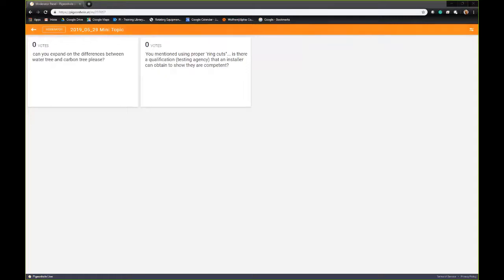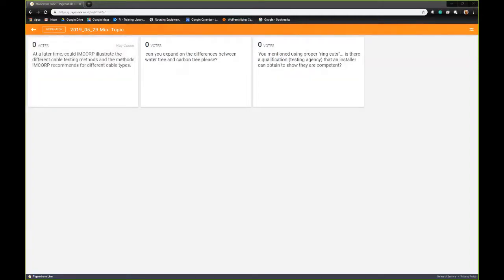Now, a carbon tree is creating the direct path between the inner conductor and the outer conductor. So that's your main conductor, and that's your semicon material or your shield that is creating that path. When you hit an inception voltage, it begins to grow that carbon tree. And that carbon tree, unlike a water tree, would typically go very vertically and directly to the outer conductor, or vice versa. It can go from the outer into the inner conductor. So the difference is one will fail a cable ultimately. The carbon tree will fail a cable, the water tree won't. The carbon tree is nothing more than a path, a hole in that cable connecting those two conductors, inner and outer. And remember, that's why you make a cutback. You've got to separate those conductors, because if you don't, they'll flash over. When you break down that cable, that's when you'll see the path.